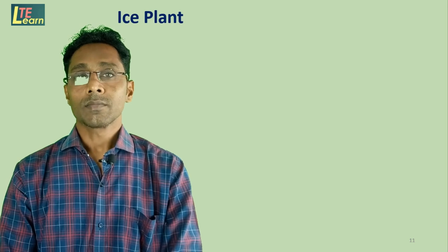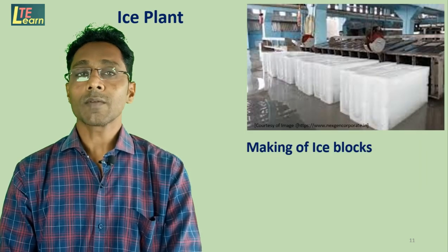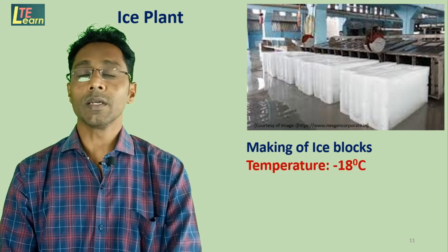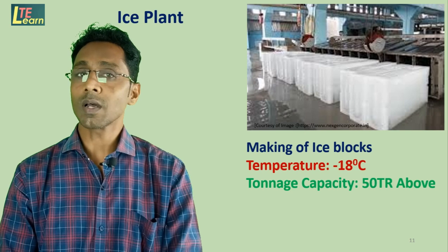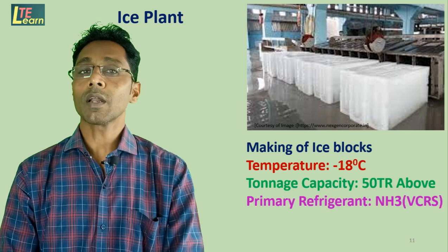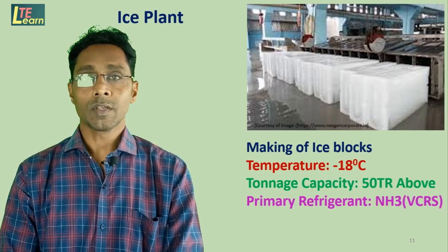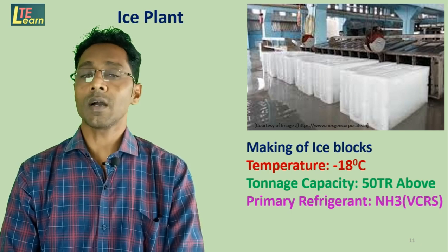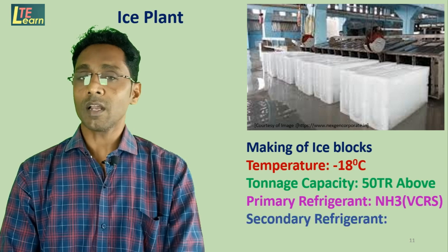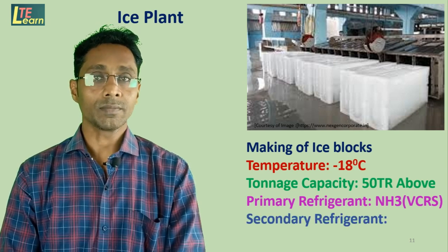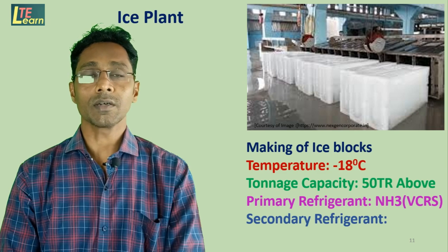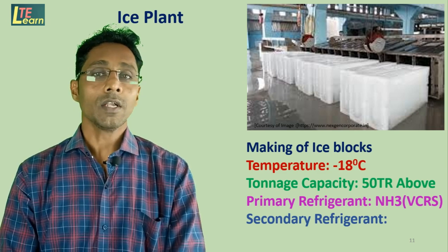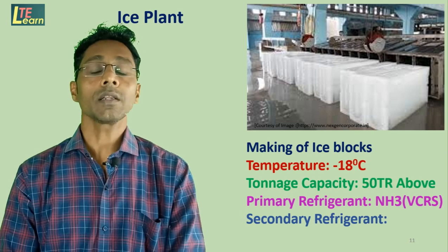Ice plant: For the making of ice blocks, an ice plant is used. The temperature requirement is minus 18 degrees Celsius to produce ice blocks. Two refrigerants are used here: a primary refrigerant used in VCRS, which is ammonia, and a secondary refrigerant cooled by the primary — called brine solution, which is a solution of water and sodium chloride or ethylene glycol.